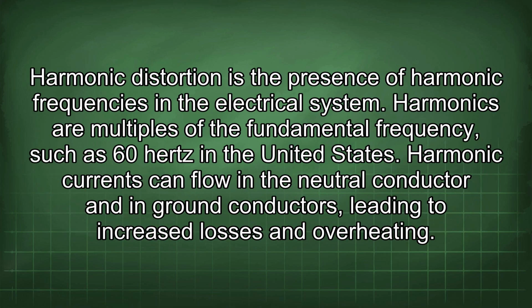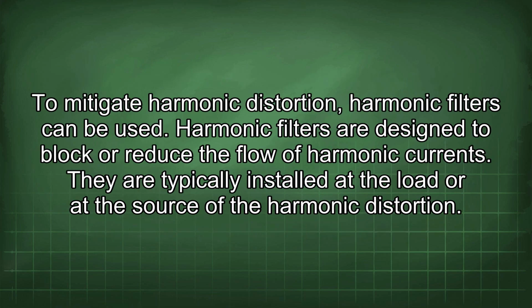Harmonic distortion is the presence of harmonic frequencies in the electrical system. Harmonics are multiples of the fundamental frequency, such as 60 Hz in the United States. Harmonic currents can flow in the neutral conductor and in ground conductors, leading to increased losses and overheating. To mitigate harmonic distortion, harmonic filters can be used. Harmonic filters are designed to block or reduce the flow of harmonic currents. They are typically installed at the load or at the source of the harmonic distortion.